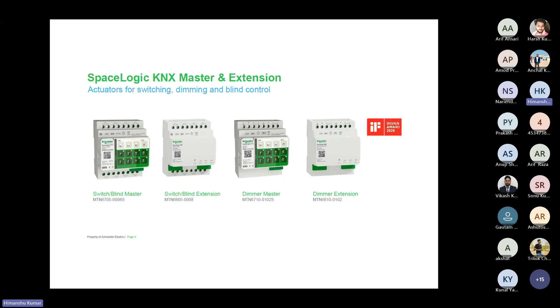What Schneider provides - many other companies provide 8 channel actuators or relays, or 12, 16, or 32 channel ones. But if a device fails, the whole 32 channel goes down. Schneider distributes it into 2 to 3 parts: if you need only 8 channels switched on, you use the master only. If you need more channels operated, you use the master and slave on both sides. This is the basic configuration we can mix and match to give cost efficiency and reduce space in the DB.